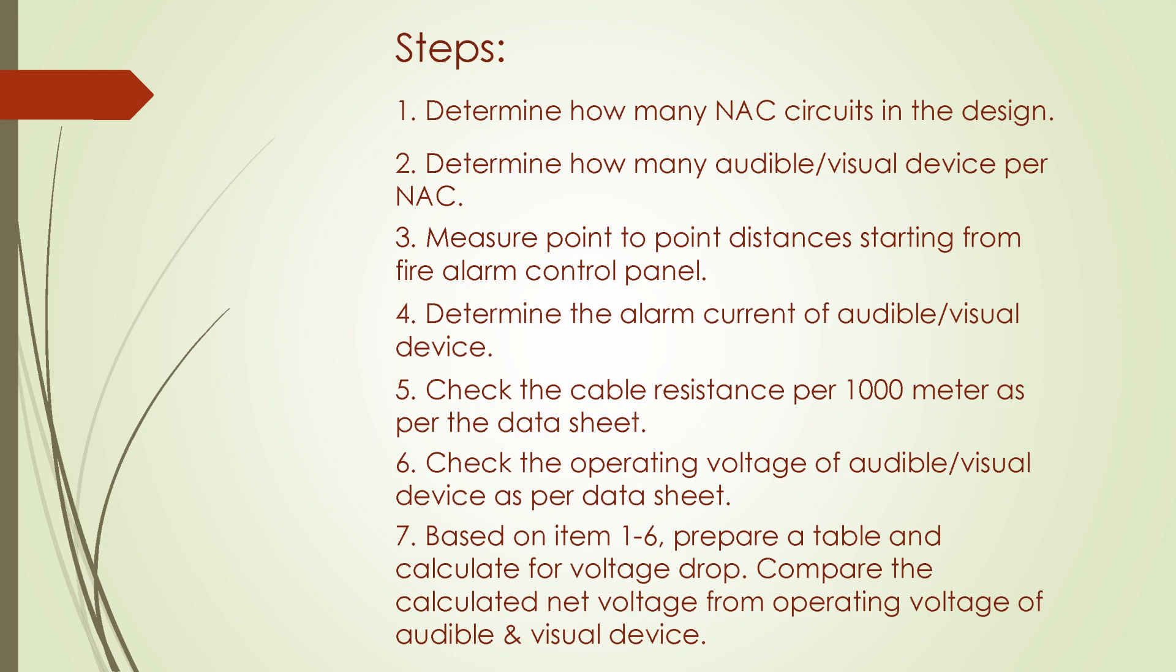Six, check the operating voltage of audible and visual device as per data sheet. Seven, based on items one to six, prepare a table and calculate for voltage drop. And the last one, compare the calculated net voltage from operating voltage of audible and visual device.